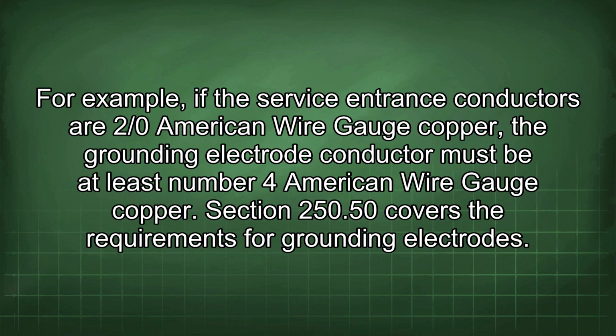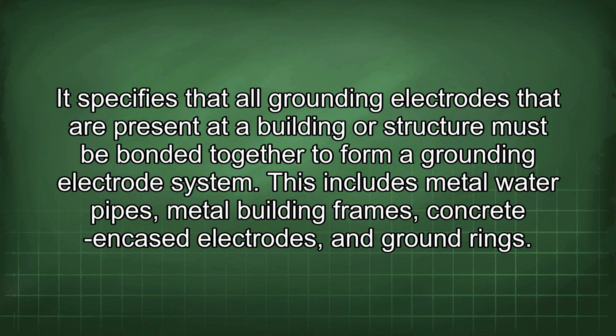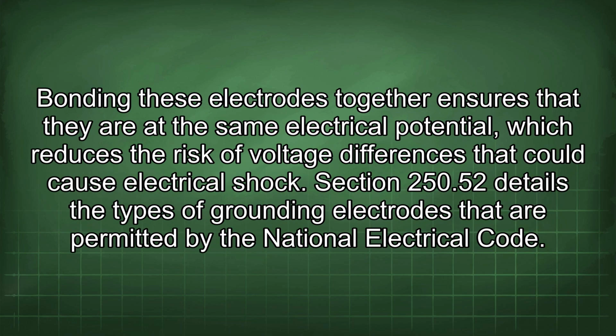Section 250.50 covers the requirements for grounding electrodes. It specifies that all grounding electrodes that are present at a building or structure must be bonded together to form a grounding electrode system. This includes metal water pipes, metal building frames, concrete encased electrodes, and ground rings. Bonding these electrodes together ensures that they are at the same electrical potential, which reduces the risk of voltage differences that could cause electrical shock.